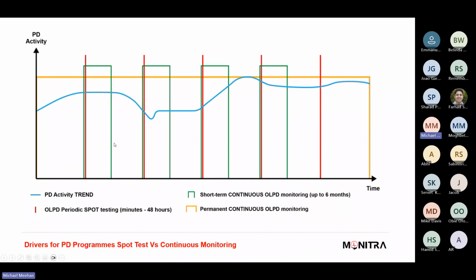I'll quickly get into data acquisition and PD. So if you think of PD, PD isn't a constant. It does vary with humidity, temperature, load, and other parameters. And that's an important thing to remember. So if you think of PD here as the blue line, over time, obviously, that PD activity will change. It can trend if there's PD activity and it's degrading. Obviously, it'll trend upwards.